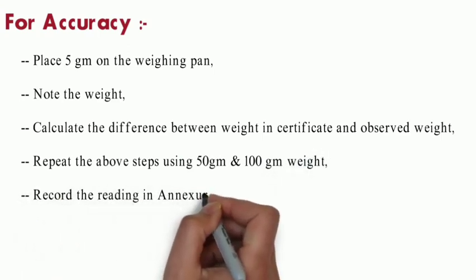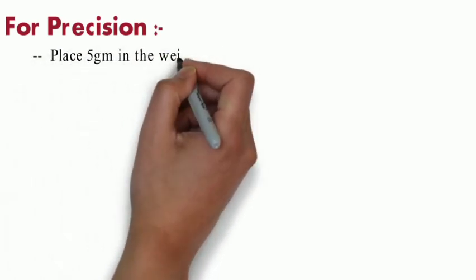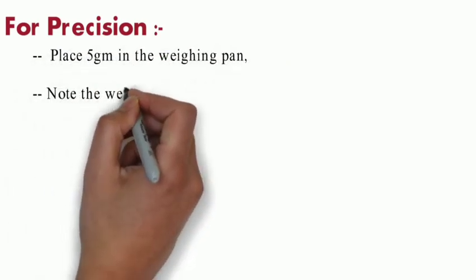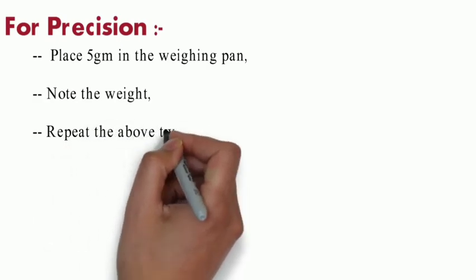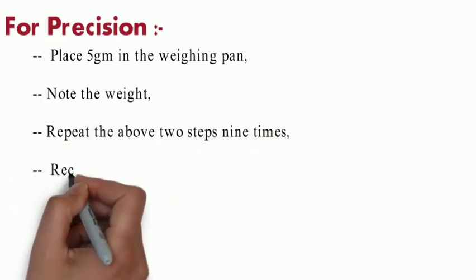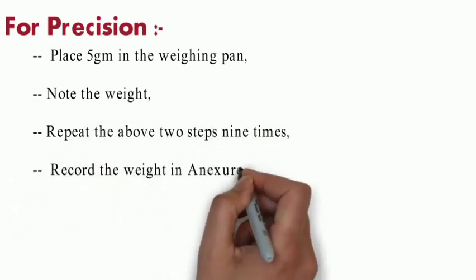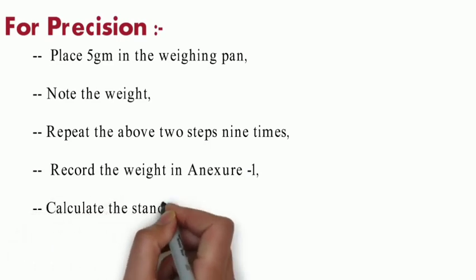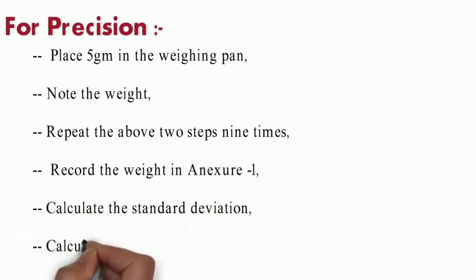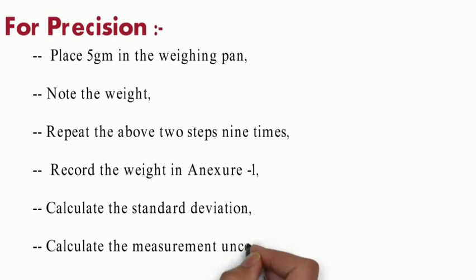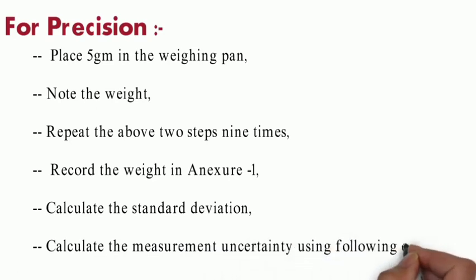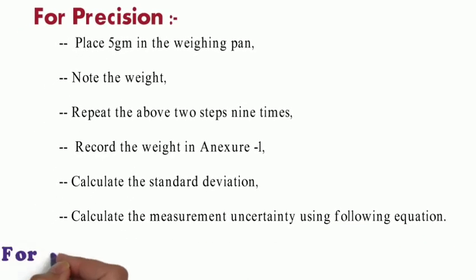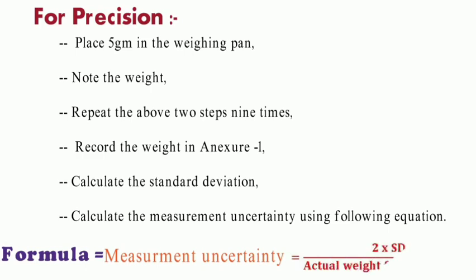For precision, place 5 grams in weighing pan, note the weight, repeat the above two steps nine times. Record weight in Annexure 1 and calculate the standard deviation. Calculate the measurement uncertainty using the following equation. Its formula is 2 into standard deviation divided by actual weight from certificate.